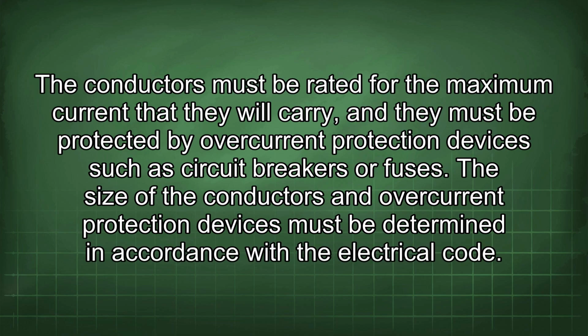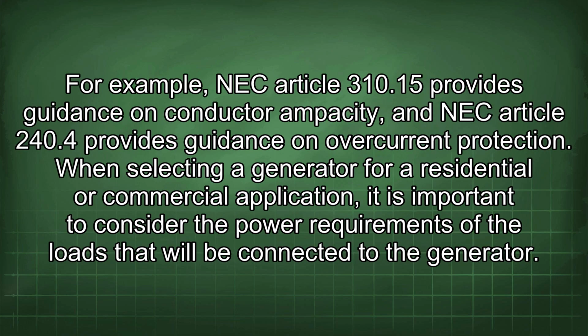The conductors must be rated for the maximum current that they will carry, and they must be protected by overcurrent protection devices such as circuit breakers or fuses. The size of the conductors and overcurrent protection devices must be determined in accordance with the electrical code. For example, NEC Article 310.15 provides guidance on conductor ampacity, and NEC Article 240.4 provides guidance on overcurrent protection.